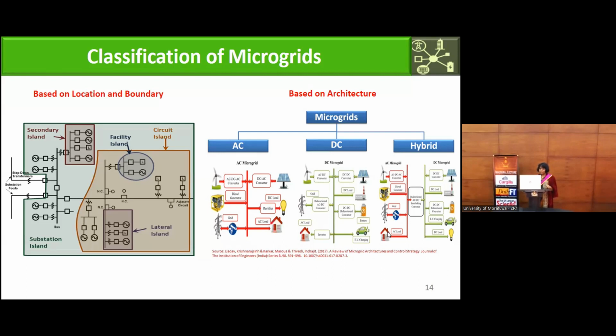The power quality is a little low. Now, the microgrid concept—it should be able to disconnect from the system, operate, and when the system is back, it must resynchronize from the system. We also experienced this with our University of Moratuwa Microgrid as well. Resynchronization back is not that easy because the voltages are not at high quality, so resynchronization problems were there.